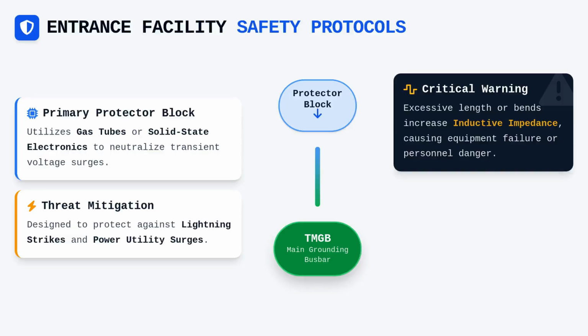If the connection path to the grounding busbar is too long or has too many bends, the inductive impedance will prevent the surge from dissipating safely, potentially damaging downstream equipment or endangering personnel. You should design this connection with a minimum bend radius and the shortest possible run to ensure that the surge arrestor functions exactly as intended by the manufacturer's specifications.